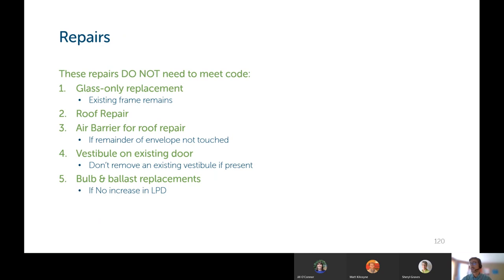Repairs. These are repairs that do not need to meet code requirements. Glass-only replacements, where you leave the existing frame in place. Roof repair, air barrier, roof repair, again, if the remainder of the envelope is not touched. Vestibule on an existing door, as long as you're not removing a vestibule that was there previously, you've got to keep it there. And bulb and ballast replacement, if there's no increase in the lighting power density calculation.